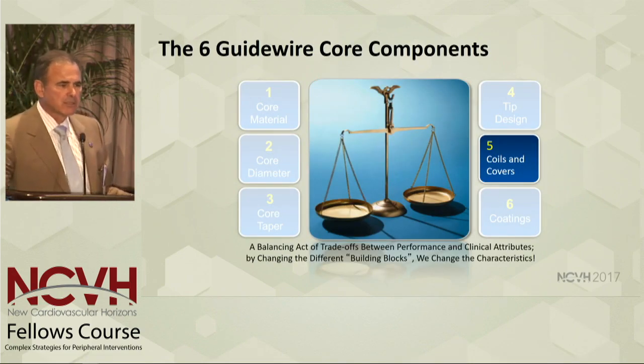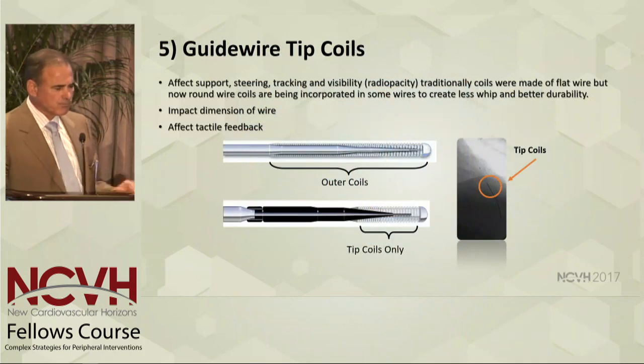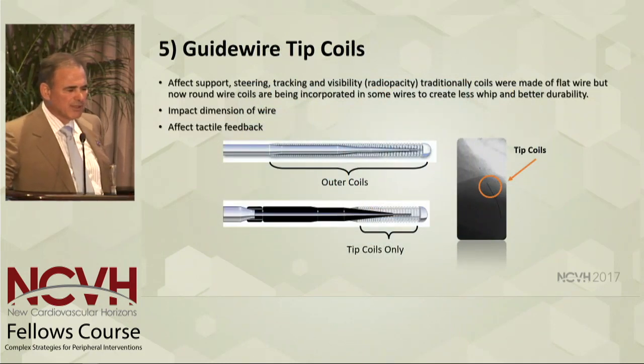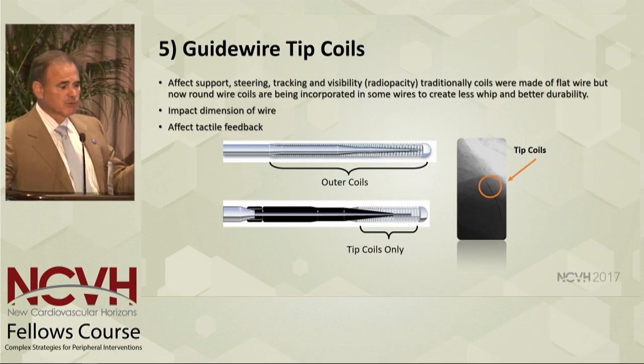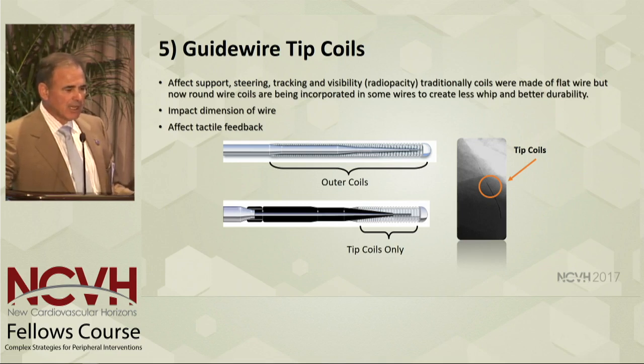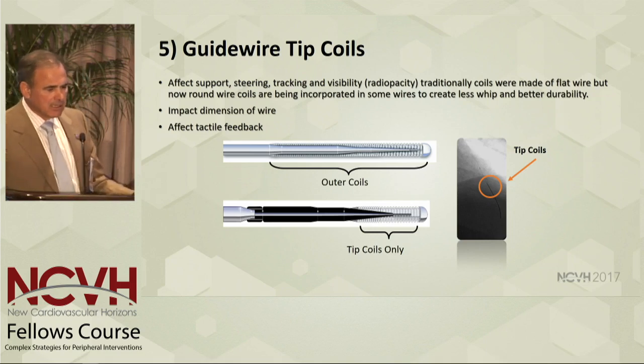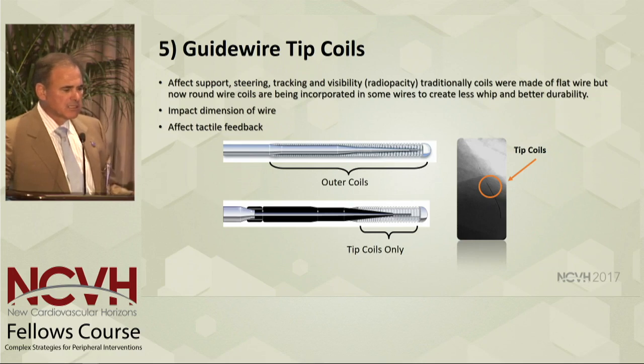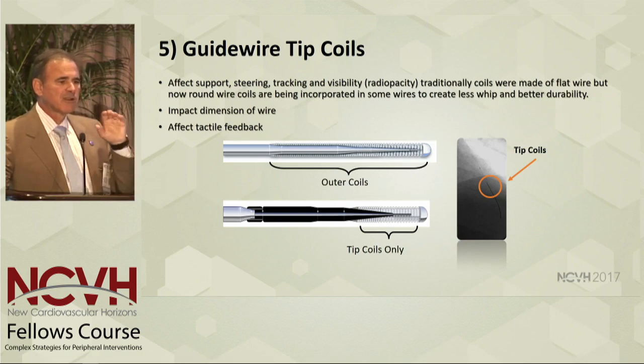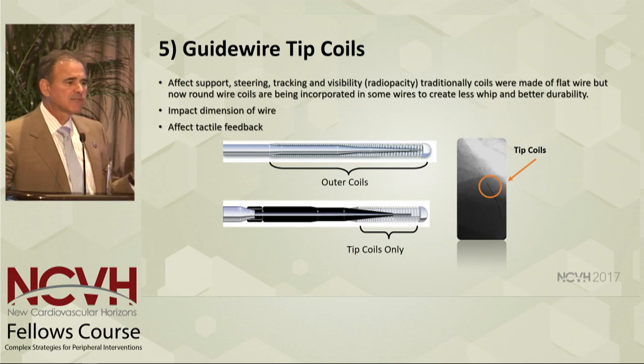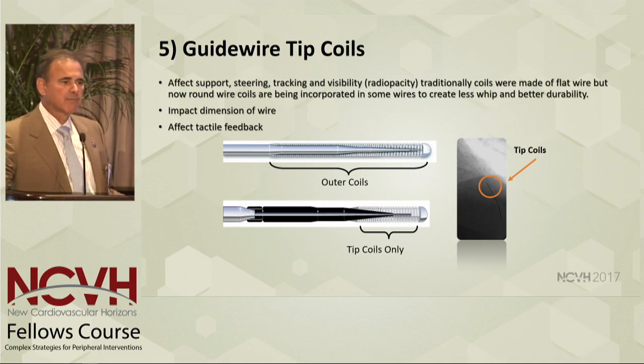In the construct of wires, we use coils and covers. Guide wire tip coils affect support, give us improved steering, and give us better tracking as you're more flexible. We have two different kinds of coils: those which are completely round and the traditional coils which are flat. Round coils give us a little bit better torque, but they do impact the dimension of the wire and thus impact tactile feedback. When we're working on a stenotic lesion, we really want maximum tactile feedback because we don't want a wire going somewhere it should not — we want to follow the true lumen.